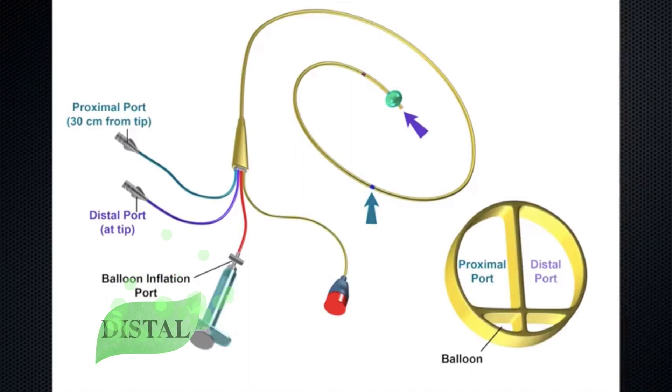The red port is the balloon port. It is used to inflate the balloon in the distal pulmonary artery, and comes with a locking guard and a pre-calibrated 1.5ml syringe. Do not replace the syringe with a regular syringe.